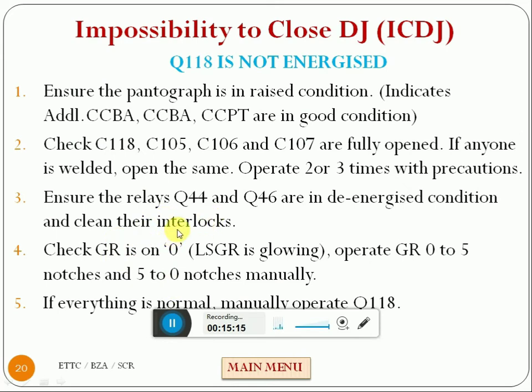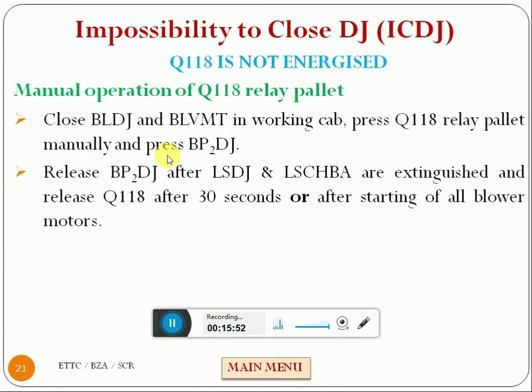So you can see here, it is impossible to close DJ with Q118 not energizing. So ensure the pantograph is raised and touching the OHE. CCBA, CCPA, CCPT and battery are all good. Ensure C118, C105, 106, 107 are fully open. Q46 interlocks: in dirty condition, clean the interlocks of Q44 and Q46. Manually operate GR 0 to 5 notches and 5 to 0 notches. Everything normal, go for Q118 manual operation.